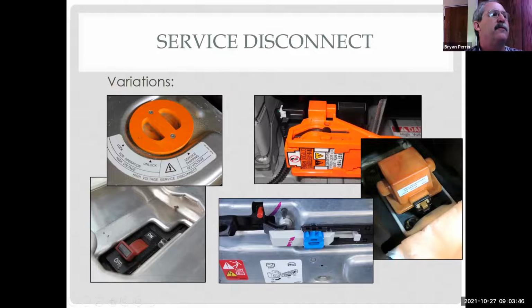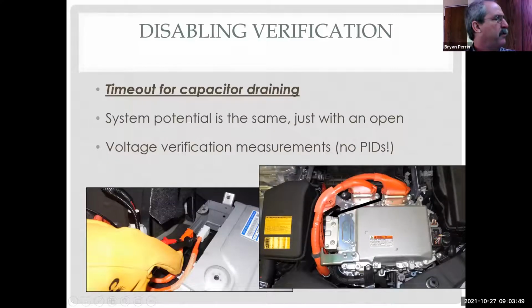We always want to verify a system is disabled. So if I'm going to verify it's disabled, I'm going to use a voltmeter with Cat 3 or 4 leads and verify there's no voltage present. Once I verify there's no voltage present, then I can take off the safety gloves.